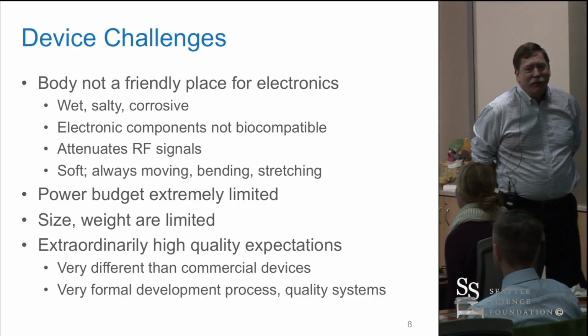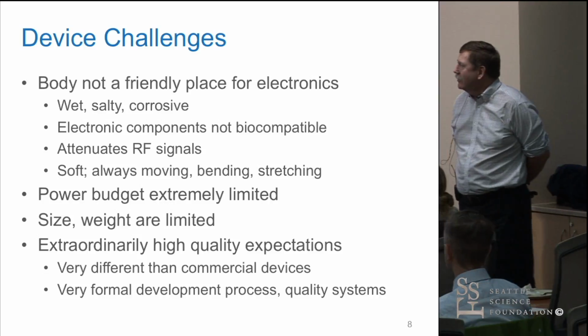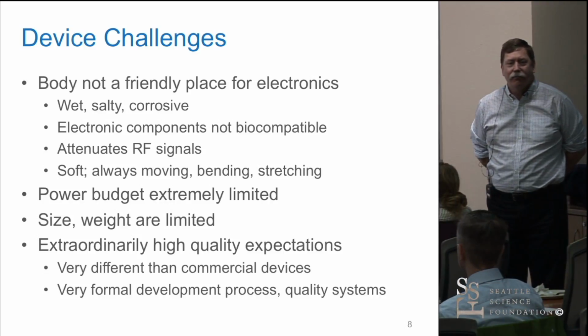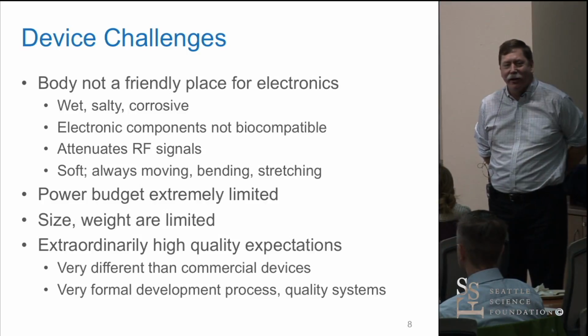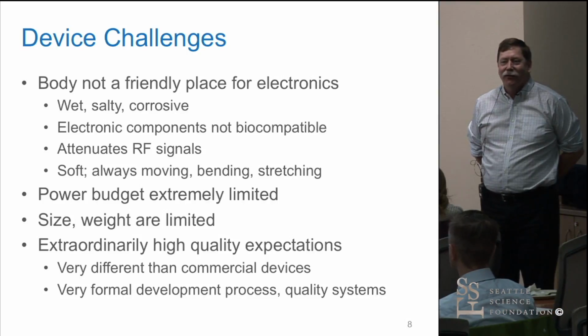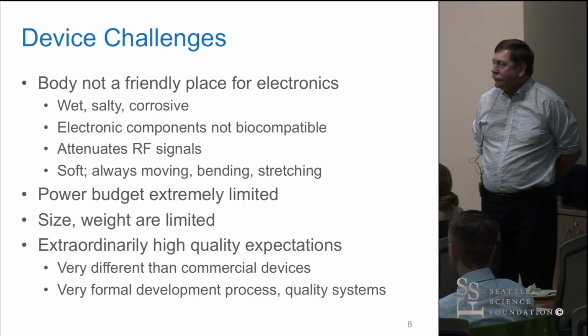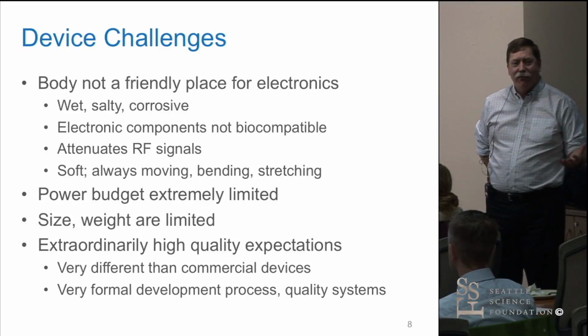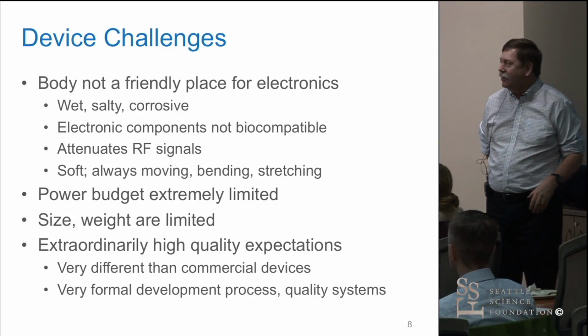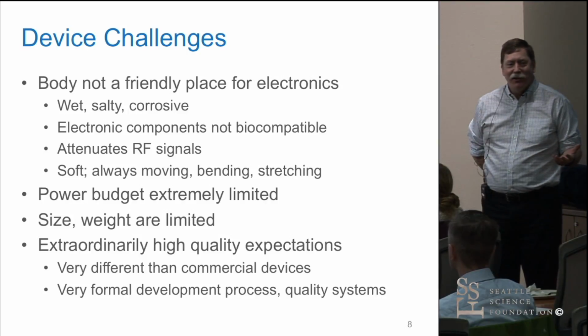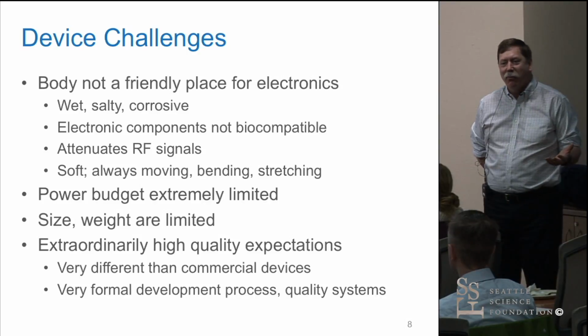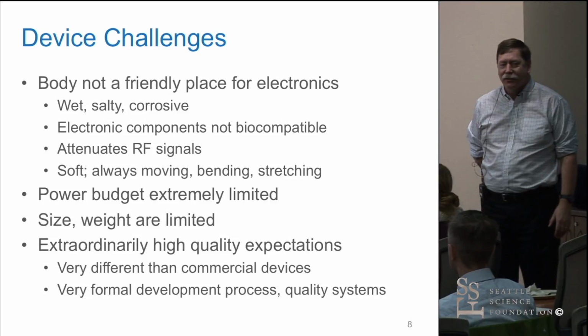There's a lot of challenges that come with devices, and I think that these might not be obvious to people who use devices. I know a lot of people refer to an implantable pulse generator as a battery, which doesn't necessarily convey the amount of things going on inside that device. But it's full of electronics and software, and there's a battery in there too, typically. And to put it in the body, that's not a very friendly place to put electronics. If you took your cell phone and dunked it in a warm bag of salt water, you wouldn't expect it to last very long. And the same is true for implantable electronics inside implantable devices.